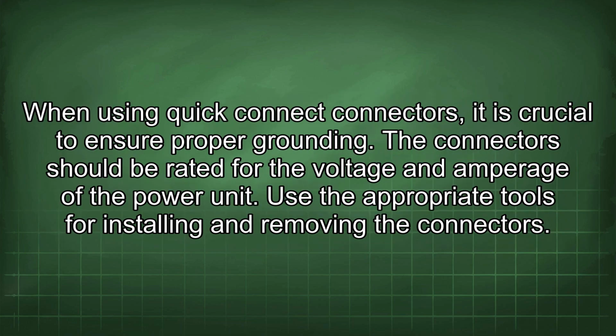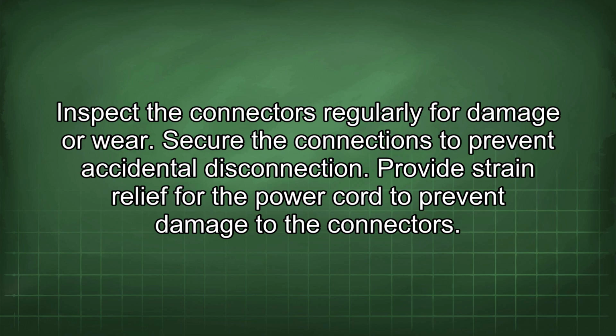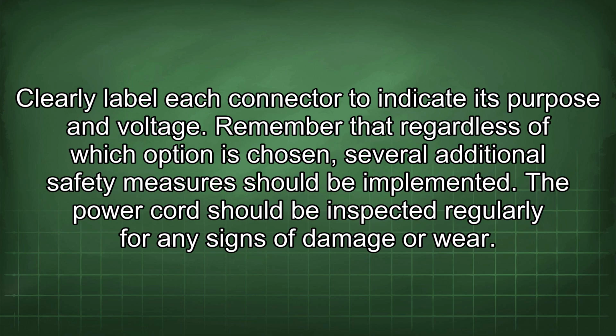When using quick connect connectors, it is crucial to ensure proper grounding. The connectors should be rated for the voltage and amperage of the power unit. Use the appropriate tools for installing and removing the connectors. Inspect the connectors regularly for damage or wear. Secure the connections to prevent accidental disconnection. Provide strain relief for the power cord to prevent damage to the connectors. Clearly label each connector to indicate its purpose and voltage. Remember that regardless of which option is chosen, several additional safety measures should be implemented.